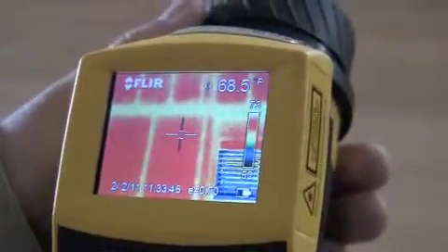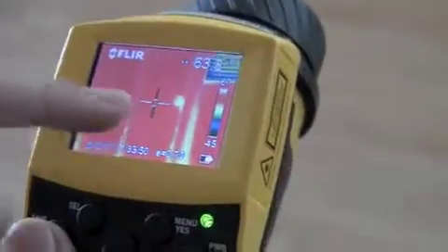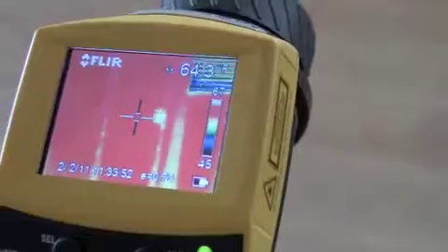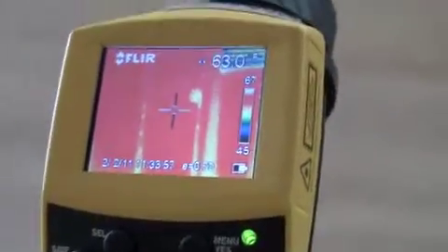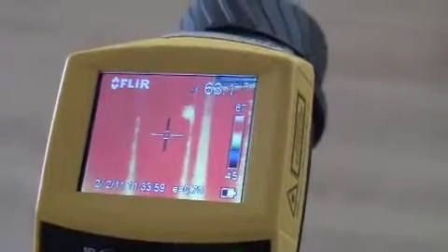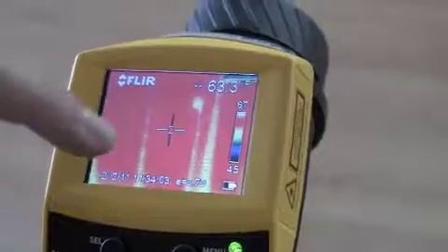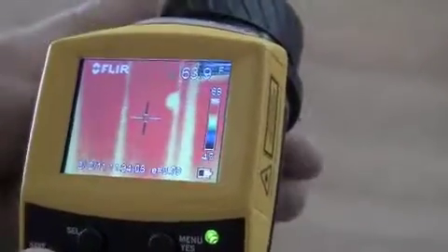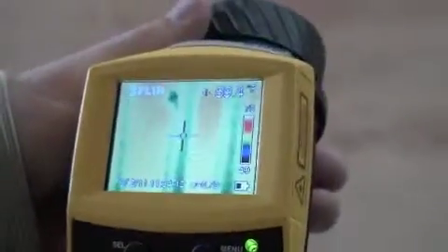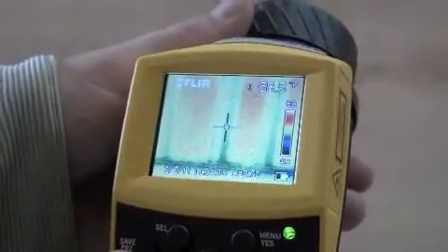However, what we see here is improper installation also, where the batts are not installed correctly or tucked in. So we're effectively 75% less R-value near the edges of our studs. So we can definitely tell that this home has bad insulation.